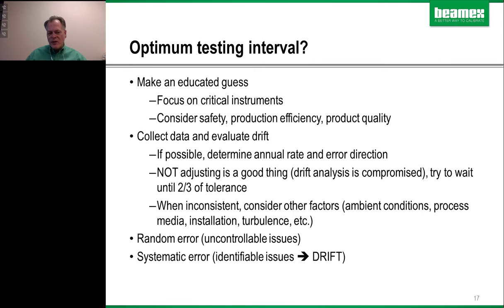And then, if you're seeing inconsistency when you're collecting this data, you need to consider what's causing this problem. Try to see if you can get a handle on it. But the goal when you're looking at this information is to try to distinguish between random error and systematic error. So random error might be ambient conditions, it might be the media, things that you can't necessarily control. But if the instrument is drifting and you're seeing a consistent change over time, that's something that you can do something about, that you can control.